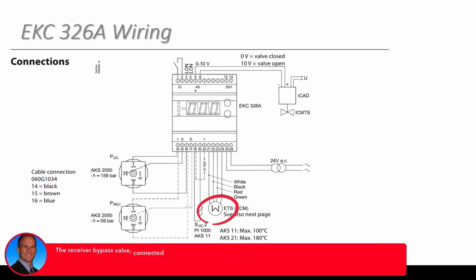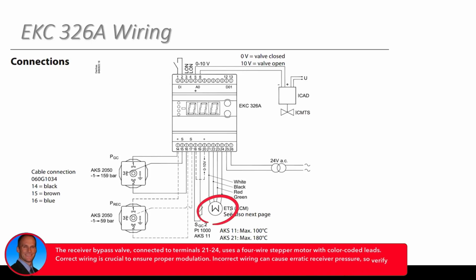Receiver bypass valve here. So I've been talking CCM, but we even had a model prior to that in ETS, which was one of our older electronic expansion valves. But regardless, it's a 4-wire stepper valve that you're going to have tied into these terminals 21 through 24. The leads coming off of the valves are color coded. So that's obviously a very important part, because these are typically bipolar motors that we're driving. So the wires have to be in the right order so that we're driving the motor we think we are, and we're driving it in the proper direction.